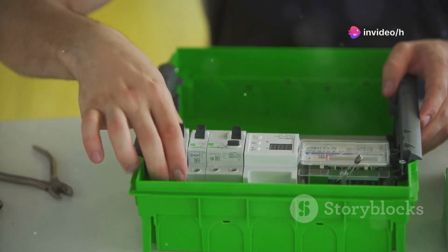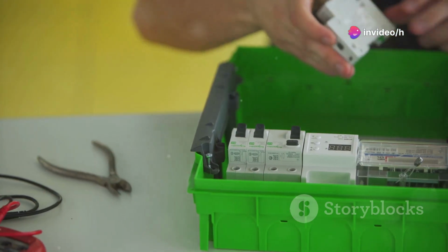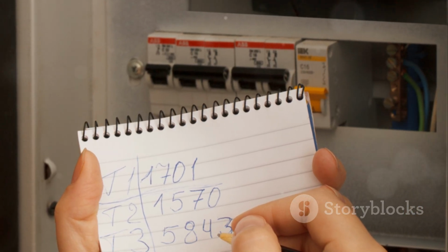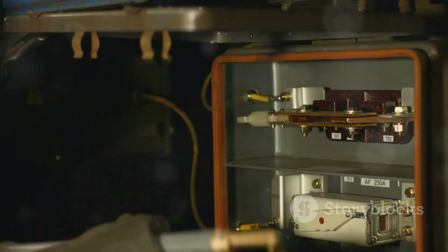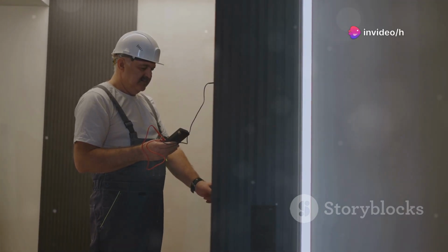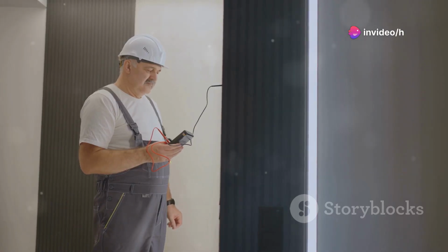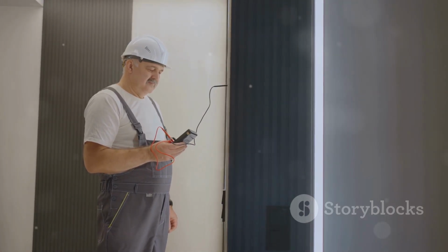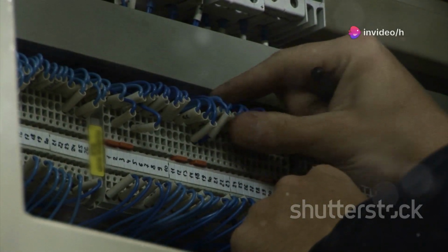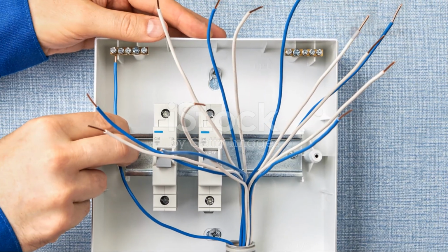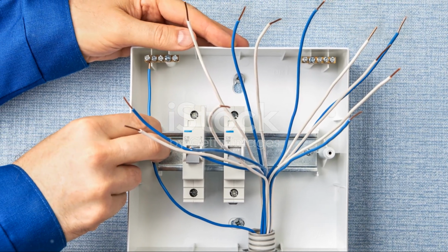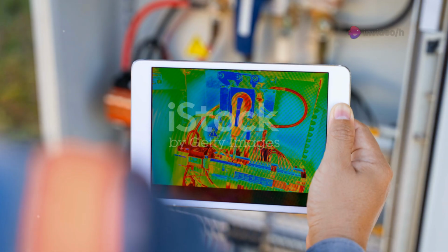Always match breaker ratings to the wire size and the expected load. Never guess or assume. Using the wrong rating can lead to overheating, equipment failure, or even fire. Double-check every connection and rating before moving on. Remember, these safety devices aren't optional. They're essential for building a professional, reliable, and safe electrical panel. Skipping or misinstalling them puts both people and property at risk. Pay close attention to every detail during installation. Careful wiring, secure terminals, and thorough inspections at this stage can prevent costly and dangerous disasters down the line. With the core safety measures in place, your panel is now ready for the next step, protecting your motors with current controllers. Let's move forward and ensure every aspect of your system is safeguarded.